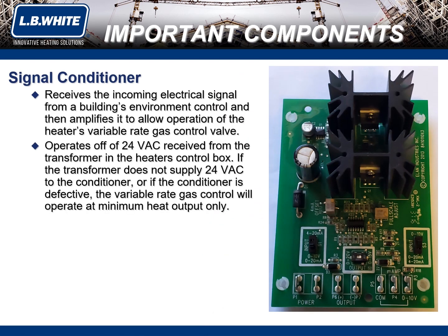A signal conditioner receives the incoming electrical signal from a building's environmental control and then amplifies it to allow operation of the heater's variable rate gas control valve. This component operates off of 24 VAC received from the transformer in the heater's control box. If the transformer does not supply 24 VAC to the conditioner, or if the conditioner is defective, the variable rate gas control will operate at minimum heat output only.